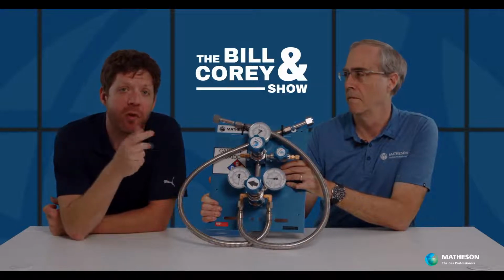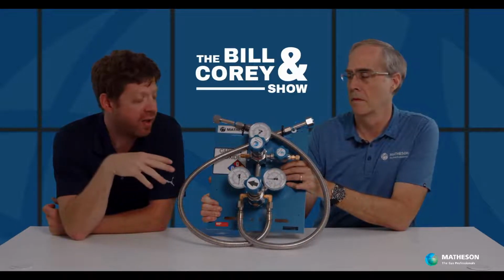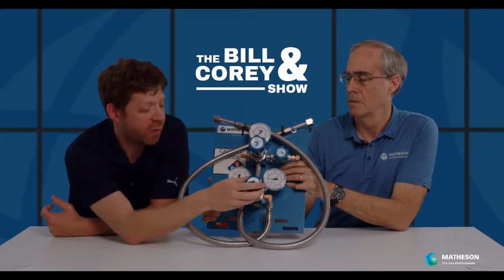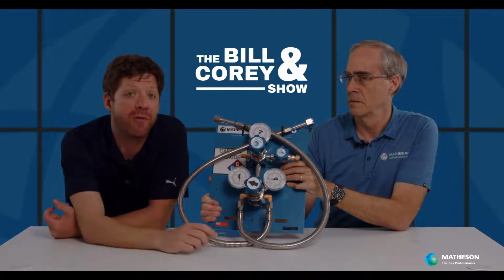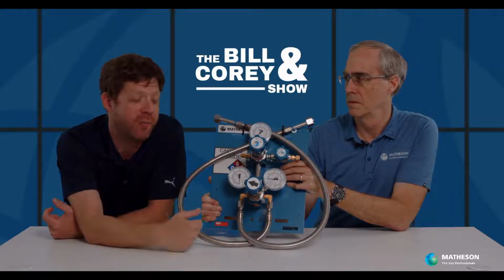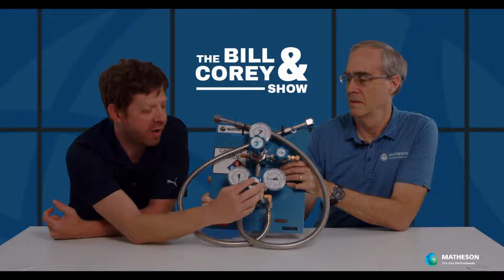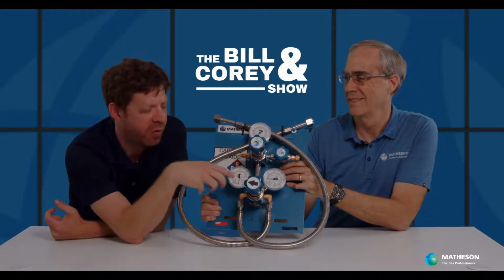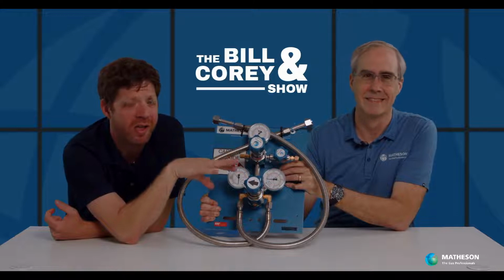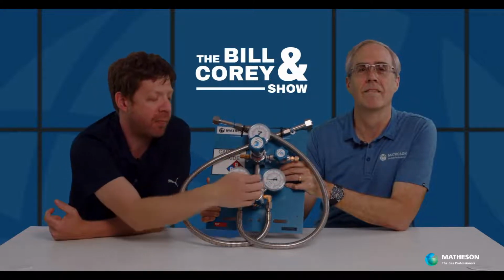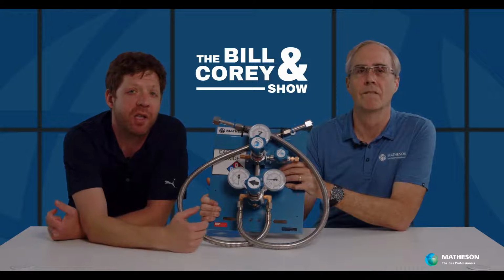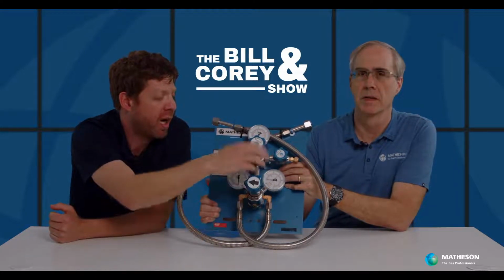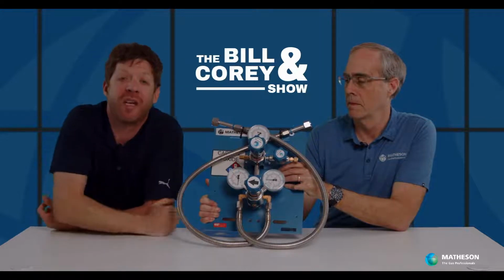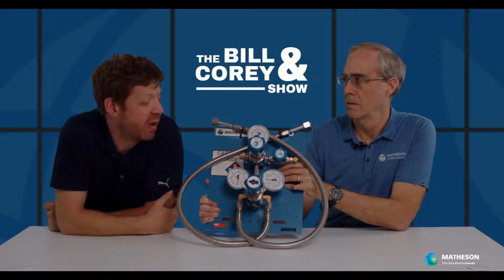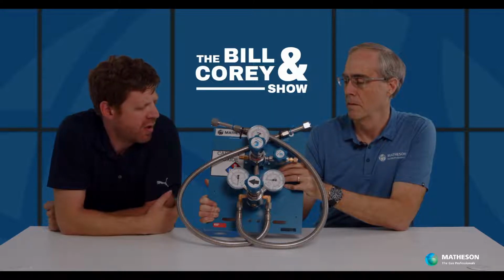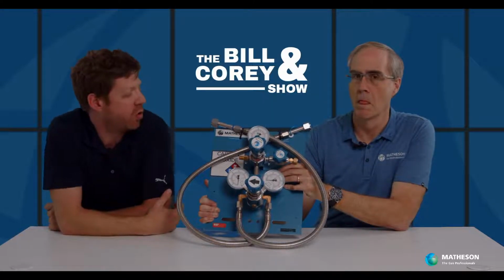Now, there's two types of dewars, of course. There's a 230 PSI max and a 350 PSI max. Our standard switchover switches over at 200, which is okay for the 350 psi max dewar, but with the 230 psi max dewar, you get a little bit of wonky in there because it's plus or minus 25 psig, which gets you pretty close to the 230. You don't want to be there. So we will bring this down to about a 170 psig max switchover pressure, and then the line regulator can only have 125 psig max instead of the 150. That's the one difference, but there's no problem in connecting a dewar to our switchover.